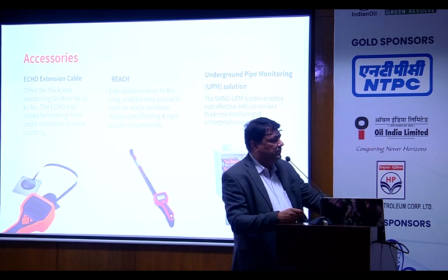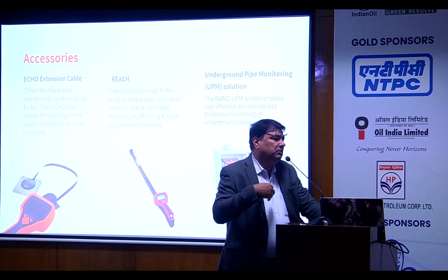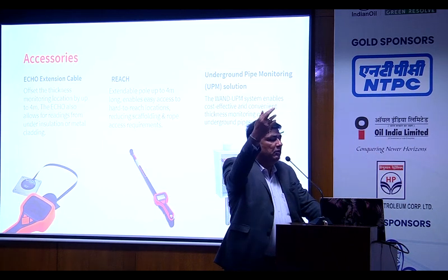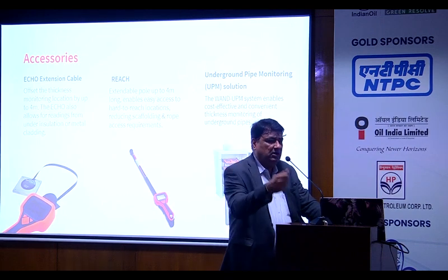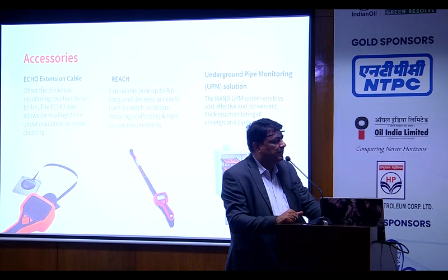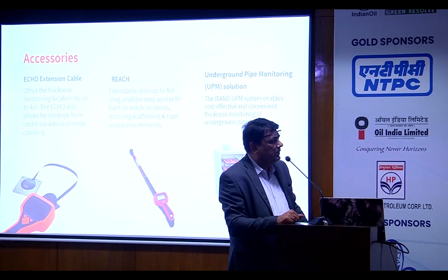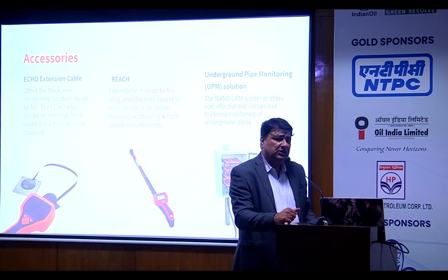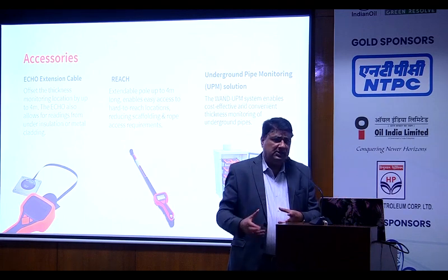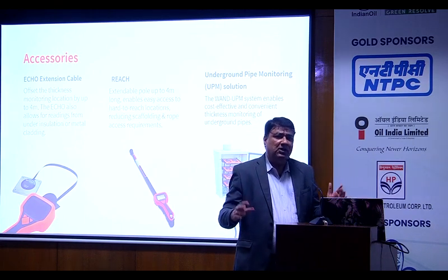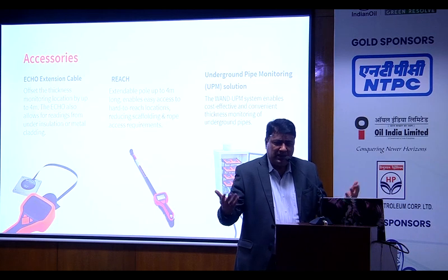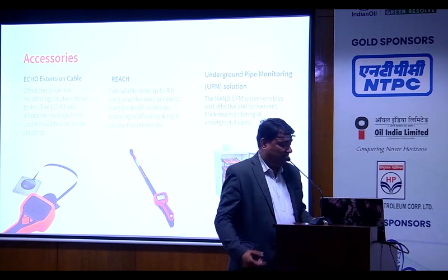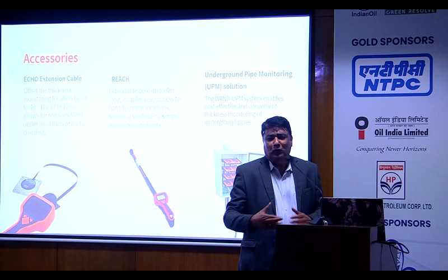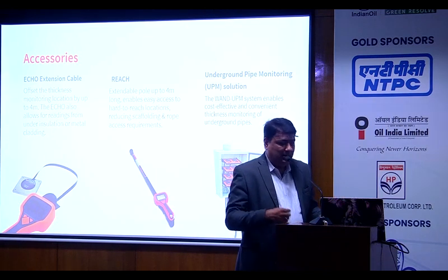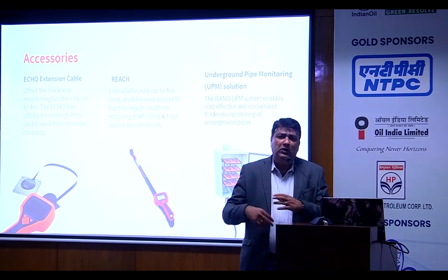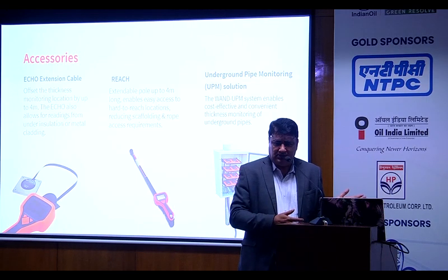The second accessory has a reach of around 4 meters, so you can mount a sensor above 4 meters and, standing on the ground, take the reading. The third is an underground pipe monitoring solution - you can mount these sensors and construct a junction box on each side of the road, giving you accurate thickness data, since with LRUT you'd have difficulty. Also, whenever you are doing repairs, you can mount these sensors.